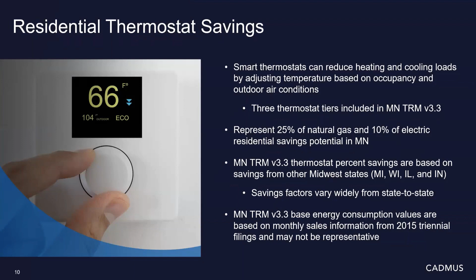So on to HVAC. First, a quick definition. Equivalent full load hours, EFLH, are equal to the total annual heating or cooling energy consumption of an HVAC unit in BTUs divided by the unit's full load heating or cooling capacity in BTU per hour. And the unit capacity is collected from manufacturer's data or equipment nameplates. HVAC equipment measures make up a large portion of potential residential savings in Minnesota as well. 28% of the natural gas potential for high efficiency furnaces and boilers, and 22% of electric potential for high efficiency air conditioning units and heat pumps.